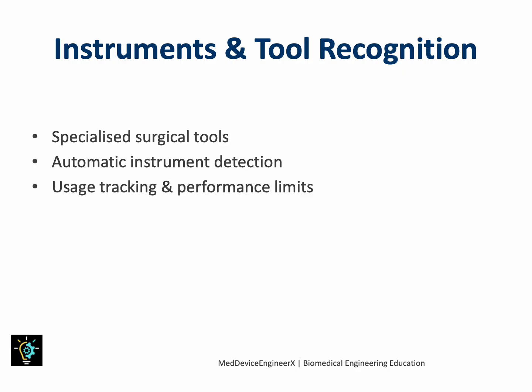This enables the system to load correct parameters such as allowable angles, torque limits, and sterility cycle counters. Many instruments have defined usage lifespans or disposable components, and the system tracks this automatically. From a biomedical engineering perspective, understanding these life cycle restrictions is very vital. So technicians must know how to inspect these engagement mechanisms, verify recognition errors, and detect early signs of any misalignment or wear. This layer of the system makes sure that the robot knows exactly what tool it's using and whether it's safe to proceed.